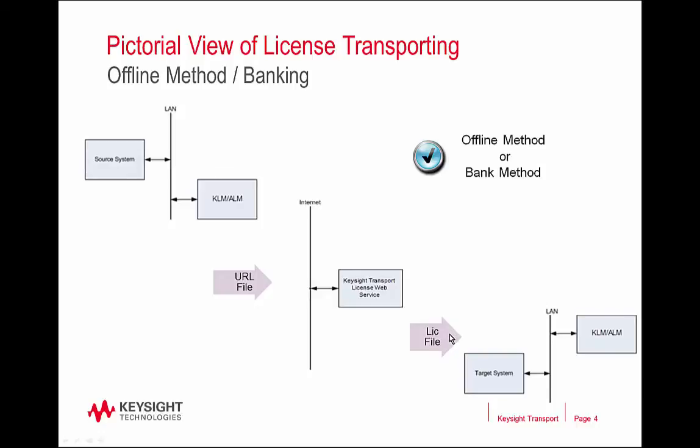We then took that memory stick and put it in the PXA Signal Analyzers in Denver, and using its internal Keysight License Manager running right on the target system, we did a file install, pointed to the files stored on the memory stick and installed the licenses.